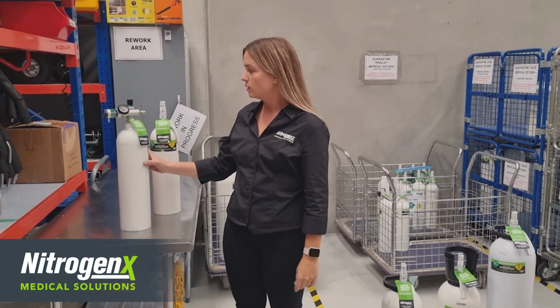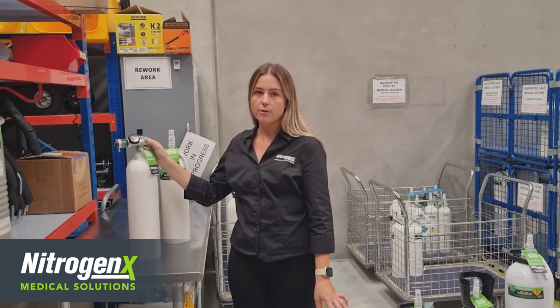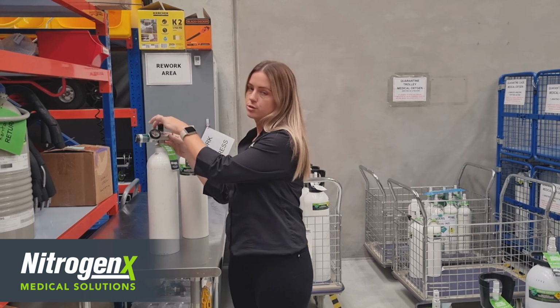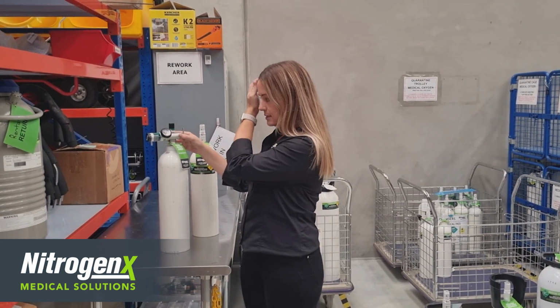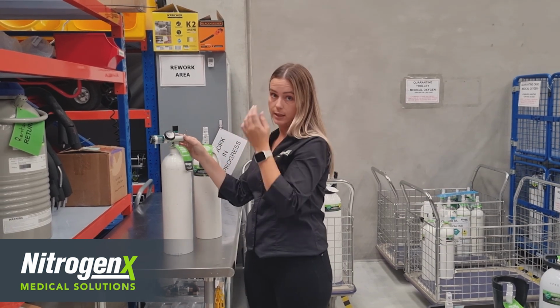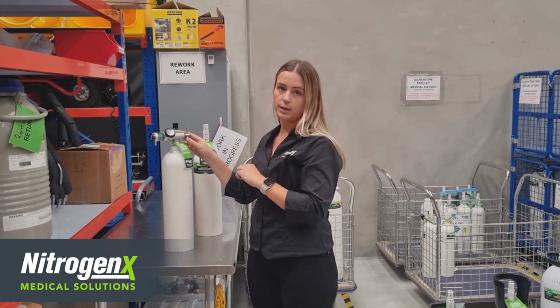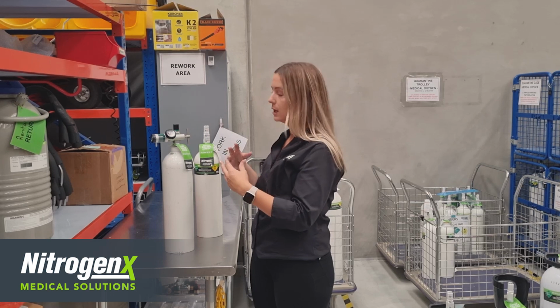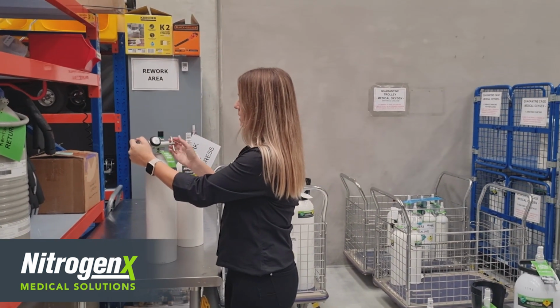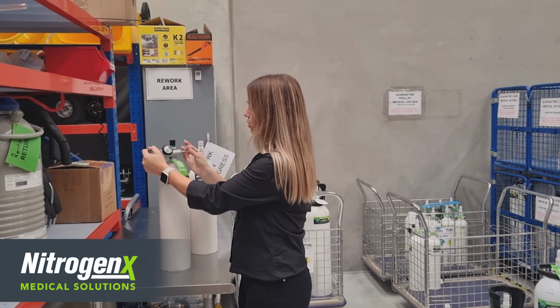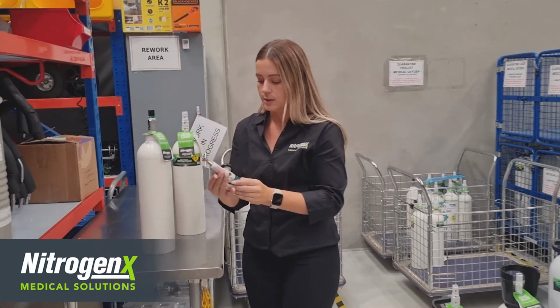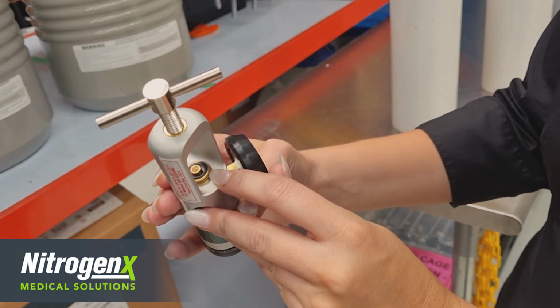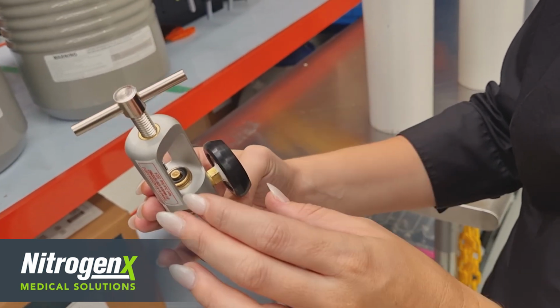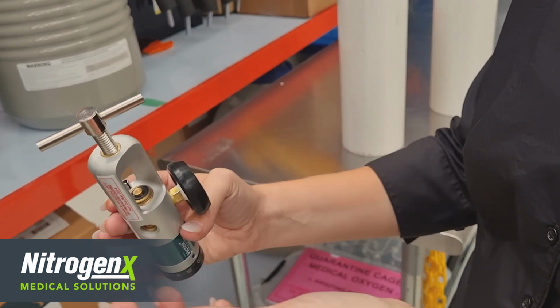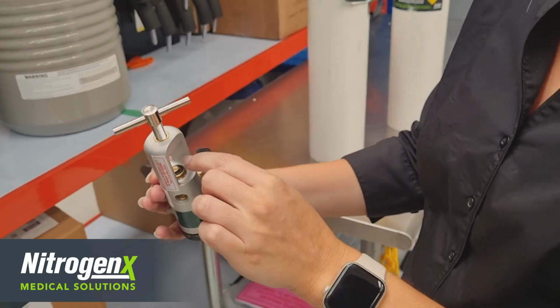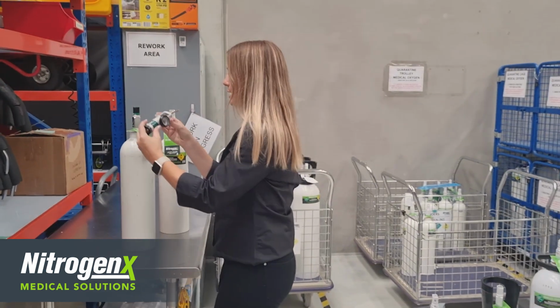If you experience a hissing or leaking of oxygen from the regulator, there's possibly two things that could be causing that. Firstly, we ask you to make sure that your oxygen is turned off. If the oxygen is turned off, it should not be releasing any oxygen as long as the regulator is attached correctly. Then we would ask you to check that the regulator is attached correctly, so again, removing everything and double checking that it is all aligned. The second option is that the metal yoke washer may not be present. Inside each regulator there is a metal yoke washer. If this is either missing or not aligned, then that will cause oxygen to leak out. If it's missing, you'd need to contact us and we can replace it for you. If it's not aligned, you would just need to put it back into place and then reattach your regulator and retest it.